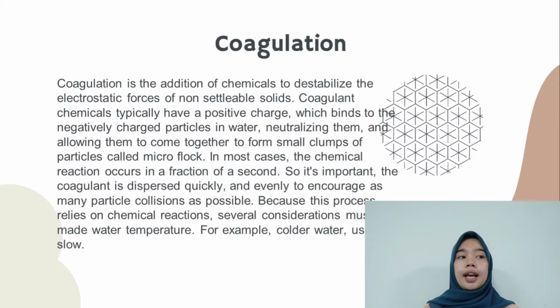Coagulant chemicals typically have a positive charge, which binds to the negative charged particles in water, neutralizing them and allowing them to come together to form small clumps of particles called microflocs. In most cases, the chemical reaction occurs in a fraction of a second, so it's important the coagulant is mixed quickly and evenly to encourage as many particle collisions as possible.